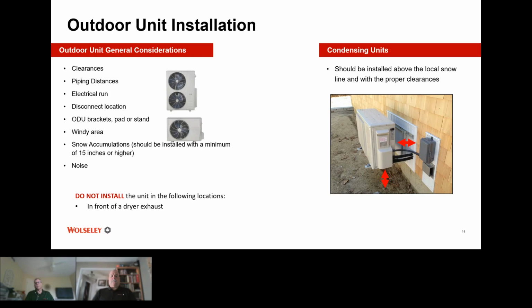Winds, again, with the winds, you may get a lot of dust and dirt and debris blowing onto the back of the unit, which all sticks on there and creates problems with your airflow. And snow accumulations, make sure it's above the snow line and you've got the proper clearance there. And if there is snow, make sure you clean around it so that it can breathe again and get lots of airflow.